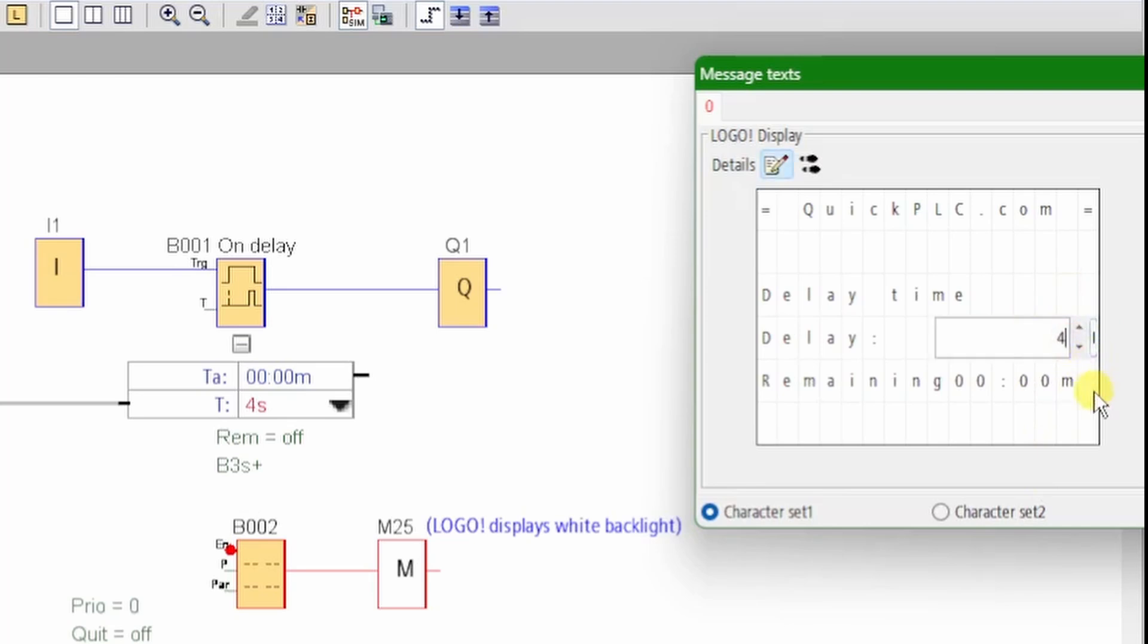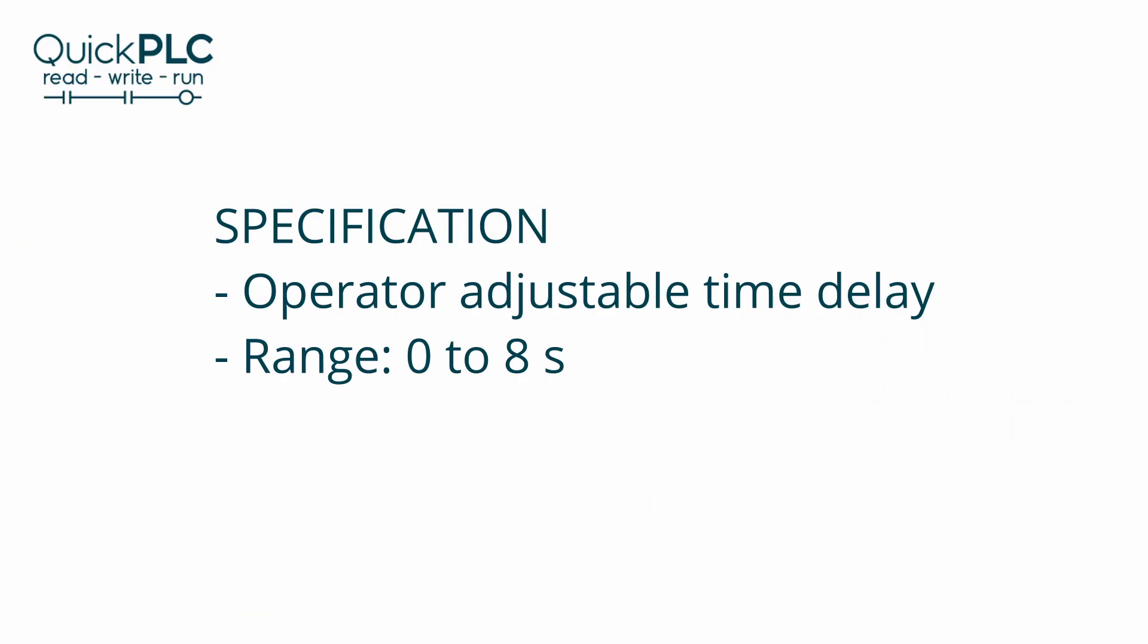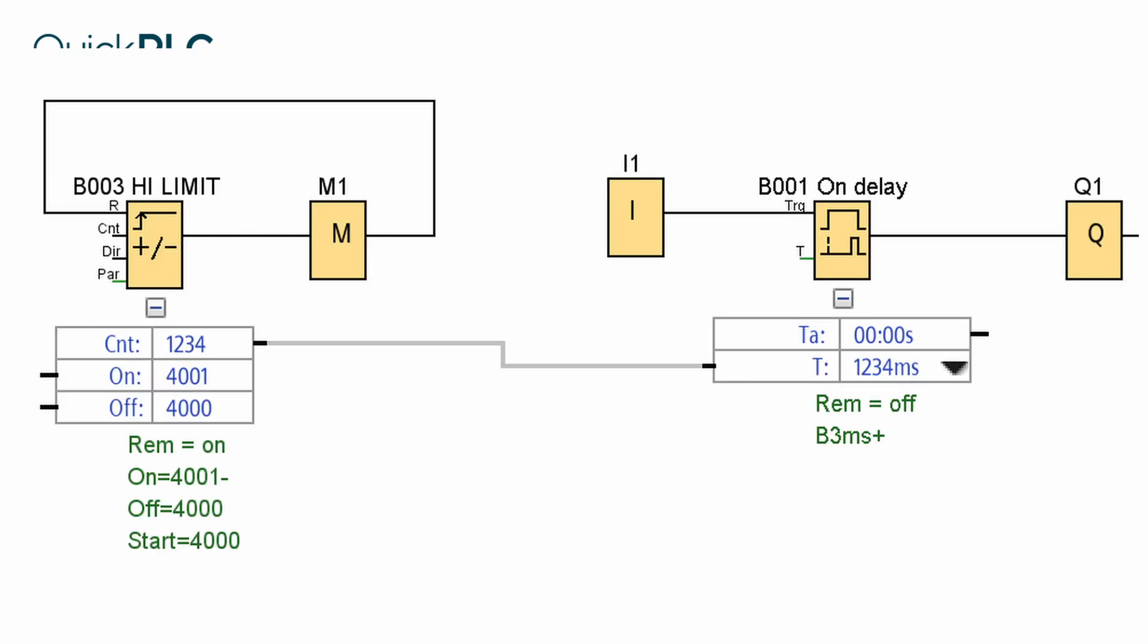Due to the logo's limited variable handling features we have to resort to trickery. In this example we want to allow the operator to set a time delay between zero and eight seconds. We can do this by allowing the operator to set a counter's current count value and passing the limited count value to the timer's T parameter.